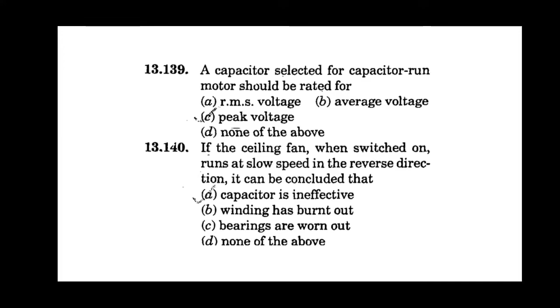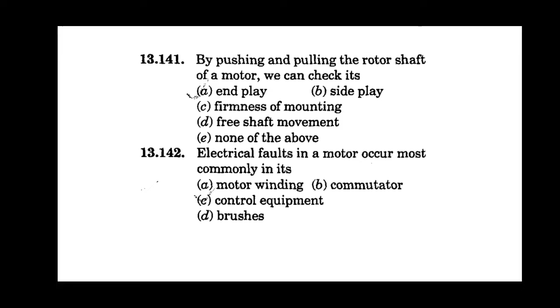If the ceiling fan, when switched on, runs at slow speed in the reverse direction, it can be concluded that capacitor is ineffective. By pushing and pulling the rotor shaft of a motor, we can check its end play. Electrical faults in a motor occur most commonly in its control equipment.